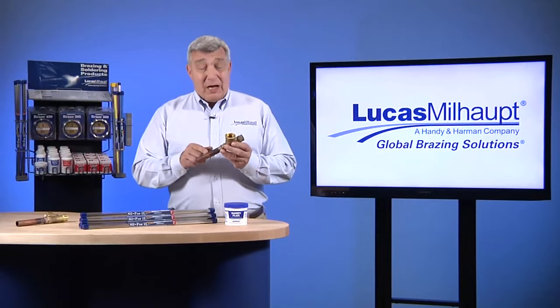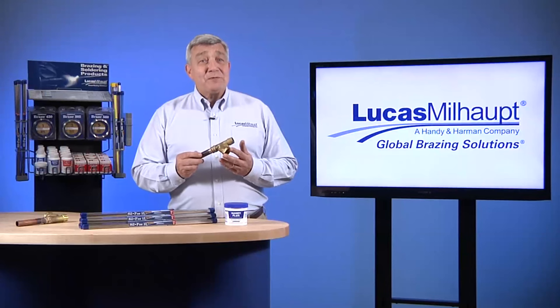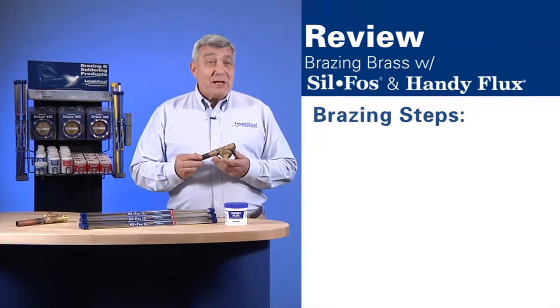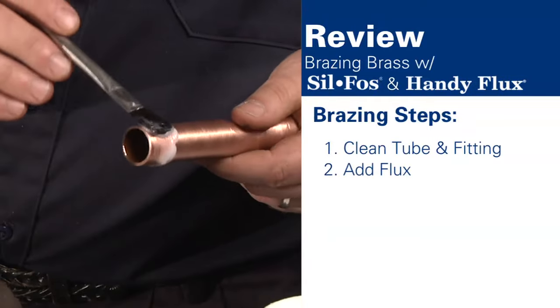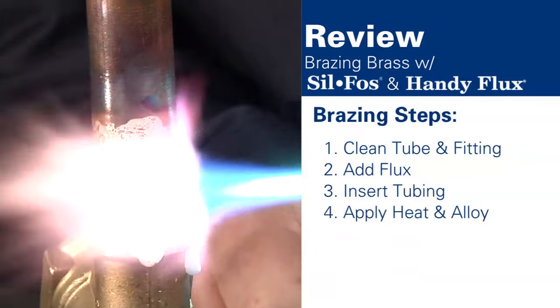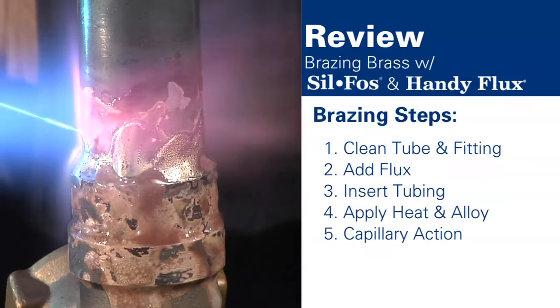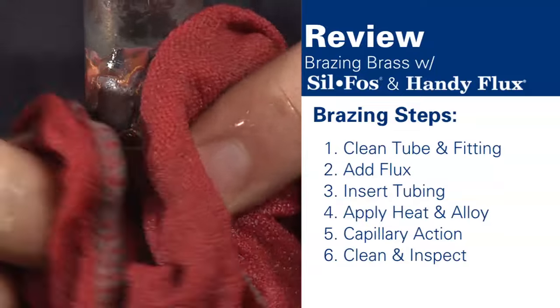As we have seen, you can braze copper tubing and brass quickly and easily with Lucas Millhaupt's Sil-Fos and Handy Flux. To review, our steps were: one, clean the tubing and fitting; two, add flux; three, insert the tubing, ensuring contact with the brass at the bottom; four, uniformly apply heat and add alloy; five, watch as the alloy is drawn around the joint; and six, clean the flux and inspect the joint.